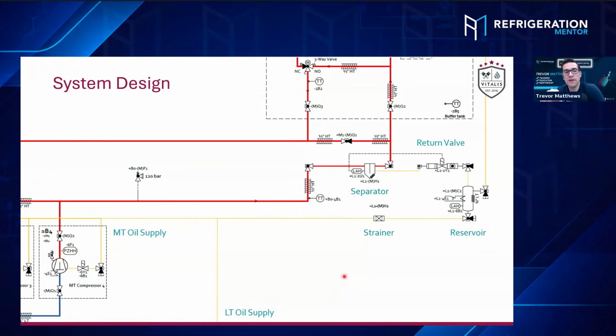Yeah, I think this is important because you've got to understand all the components for maintenance. This is one of the things that I've seen, Jonas, in all the trainings, especially with new technicians who haven't done oil maintenance before. They've done it on HFC, but they haven't done it on CO₂ yet. It is not really any different. The pressures are higher, but the oil system may have a few more filters in it. So strainers and filters are some of the things that do need to be checked, as well as probably replaced at some point. In Jonas's manual, they will tell you the intervals they want you to look at and do these tests. So it's in the checks, because that is so important.